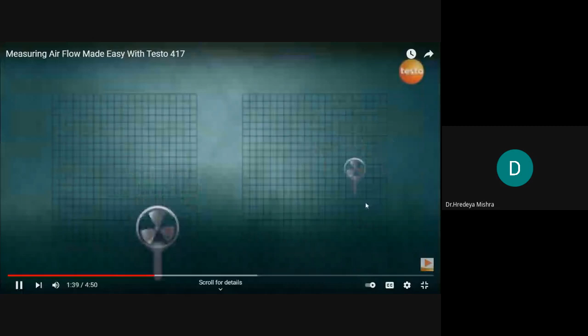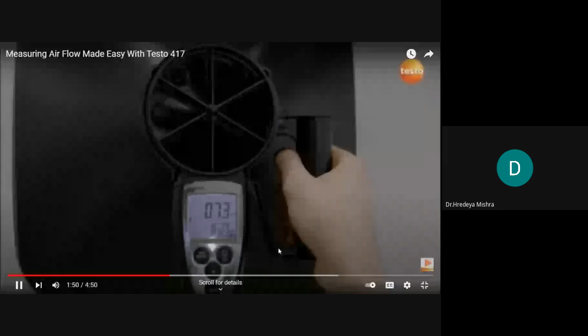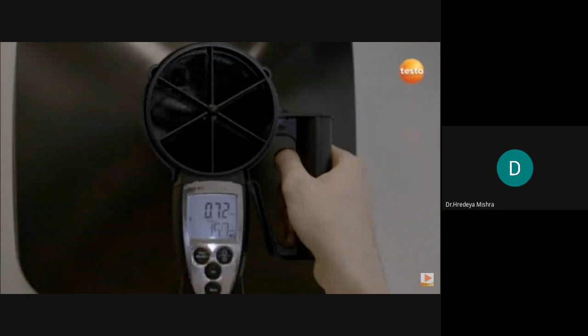The Testo 417, when used with the optional measurement funnels, allows you to measure at standard supply air outlets with more accuracy and speed. With the looping method, you have to make sure the cross-section of the ventilation outlet is traversed at a constant speed. With the funnel, on the other hand, the different air velocities are averaged. Therefore, the funnel allows you to complete measurements faster.